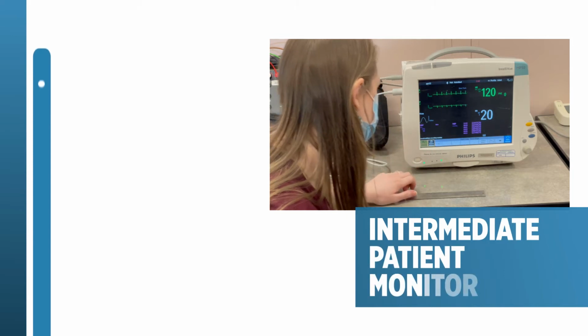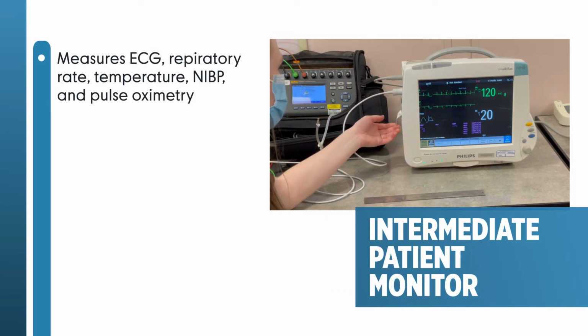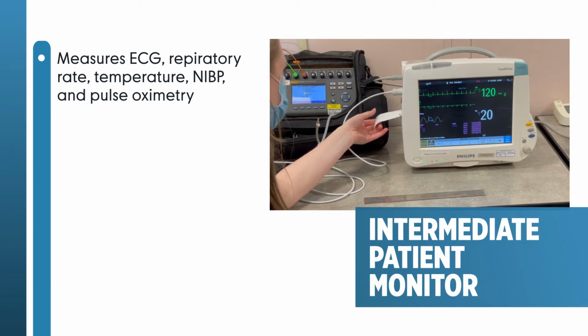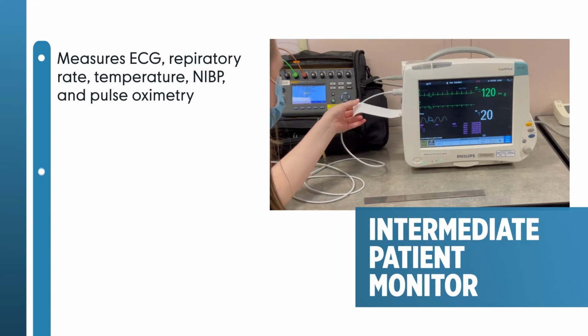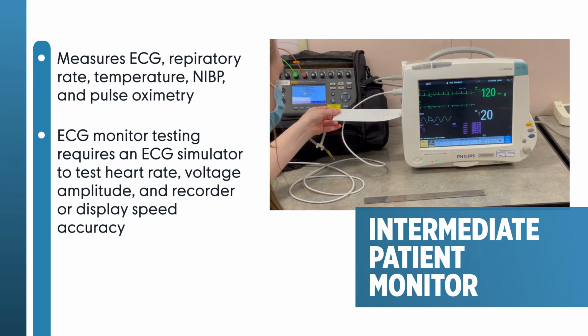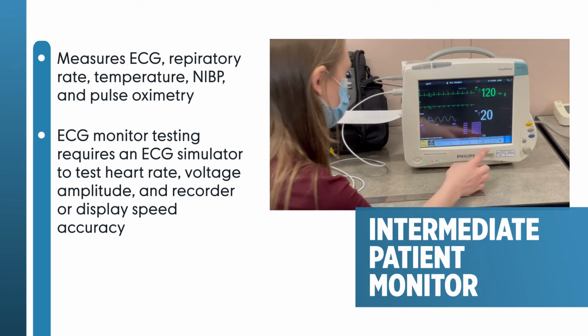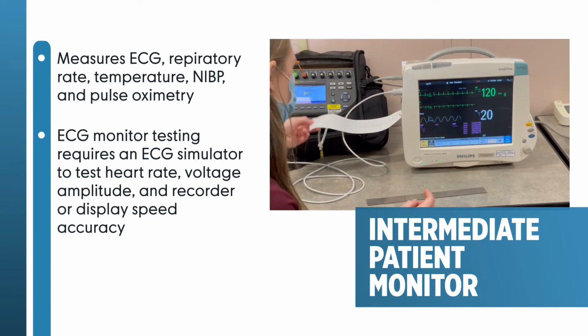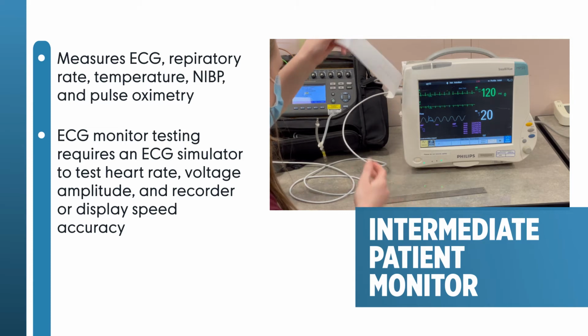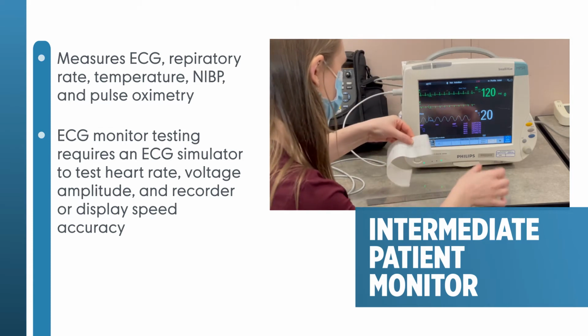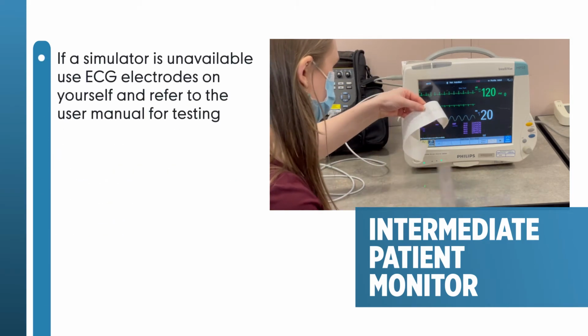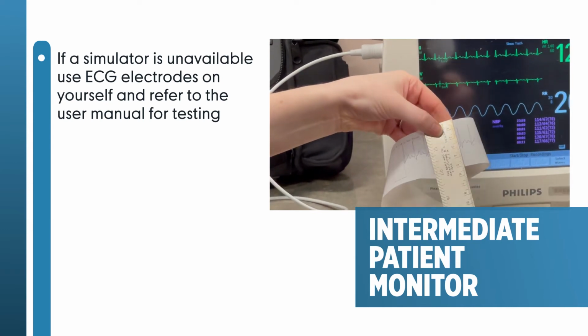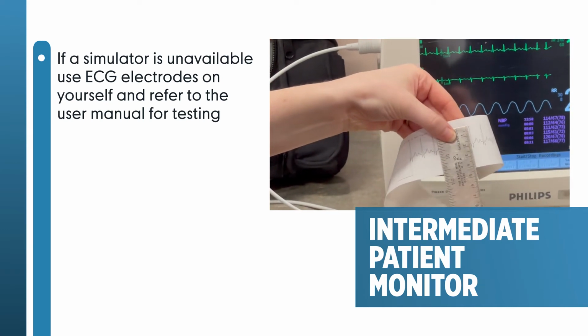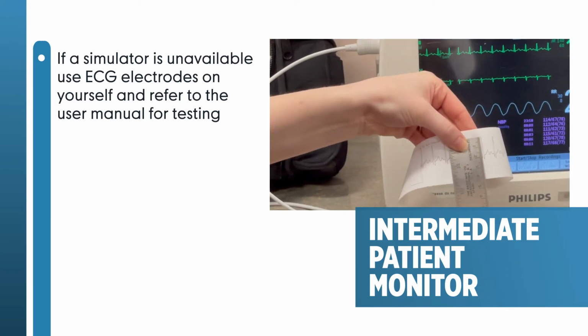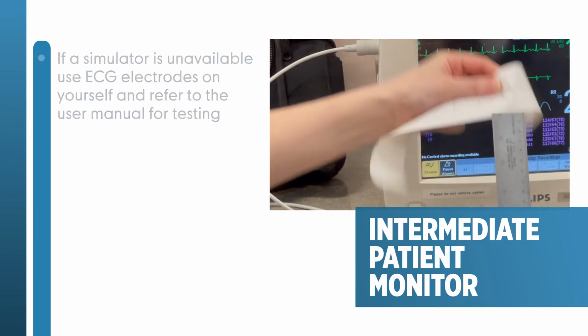Intermediate patient monitors typically include ECG, respiratory rate, and temperature, in addition to non-invasive blood pressure and pulse oximetry. ECG monitor testing requires an ECG simulator to test heart rate, voltage amplitude, and recorder or display speed accuracy. If an ECG simulator is not available, apply ECG electrodes to yourself per the user manual and observe the ECG rate versus your pulse and waveform clarity.